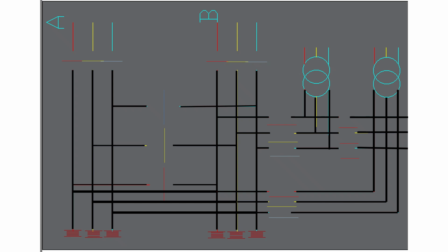In railway system, mainly we are using single phase, but nowadays it is 2 into 25 kV. Due to this 2 into 25 kV system, we are using three phases. Scott connection is using all the three phases in the transformer, but in open delta we are using alternate two phases in three transformers. There are three power transformers and alternate phases we are connecting with.